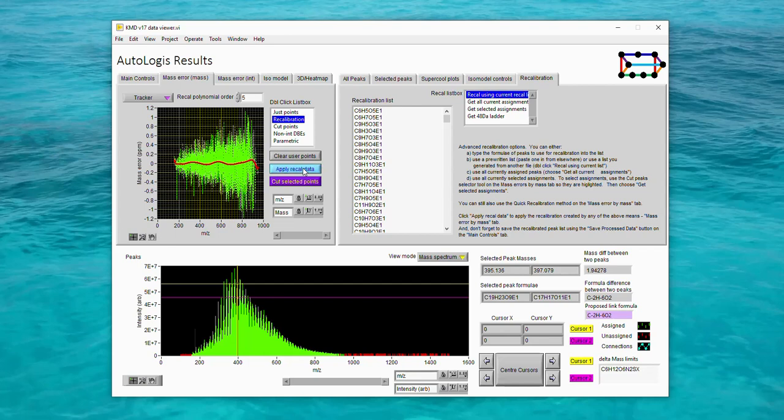While that recalibration is being applied, it's worth remembering that these types of localized mass recalibration issues can be caused by the ion density in the instrument or the mode of use of certain designs of mass spectrometer. Because in this case we're applying Tracker mode after the gross polynomial correction, we don't see a huge difference in the data, but it has had an effect.